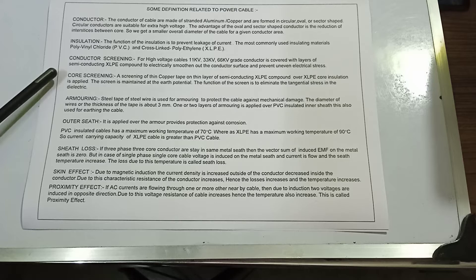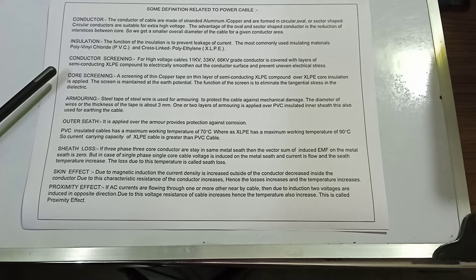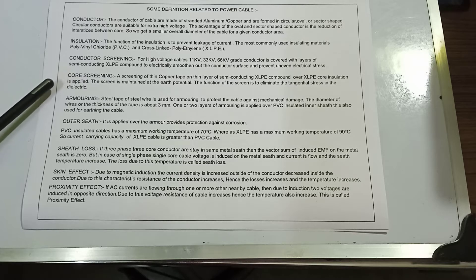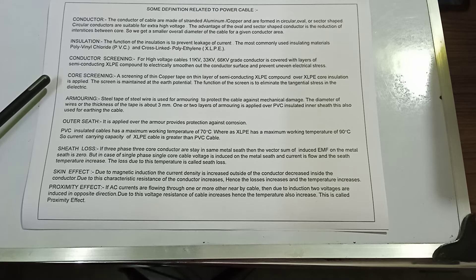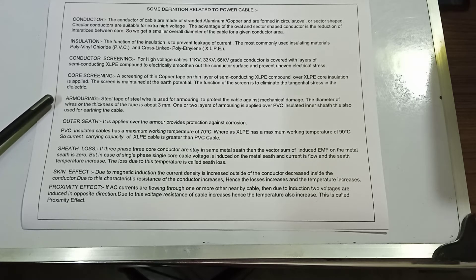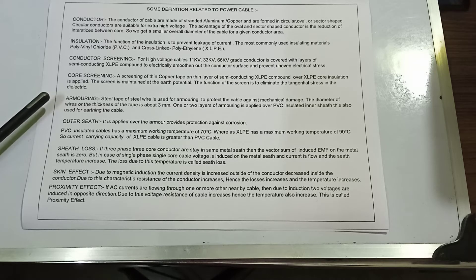Next: core screening. A screening of thin copper tape or a thin layer of semiconducting XLPE compound is applied over the XLPE core insulation. The screen is maintained at earth potential. The function of the screen is to eliminate tangential stress in the dielectric. Next: armoring. Steel tape or steel wire is used for armoring to protect the cable against mechanical damage.